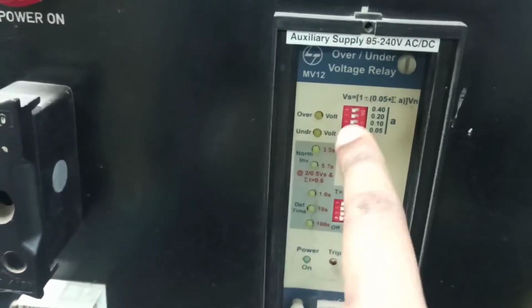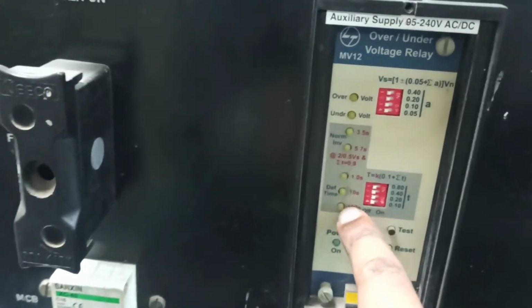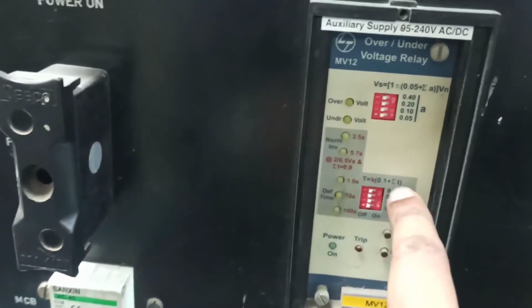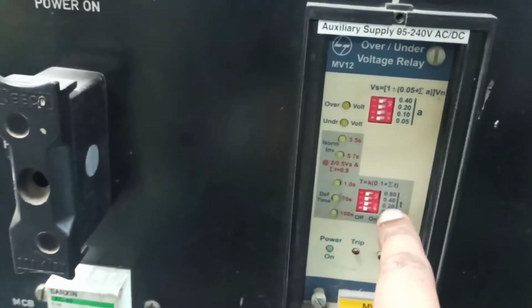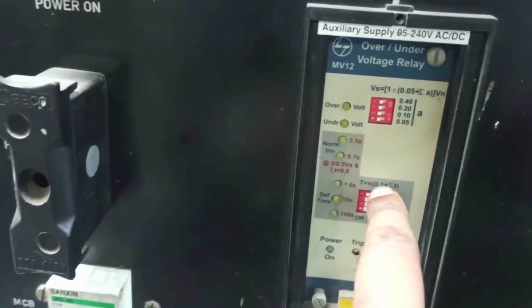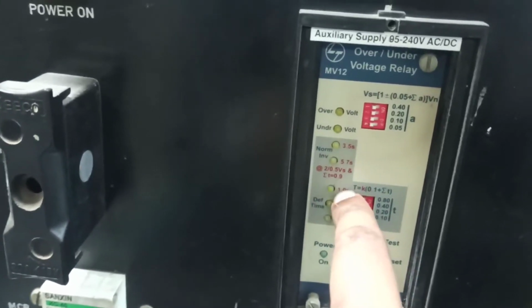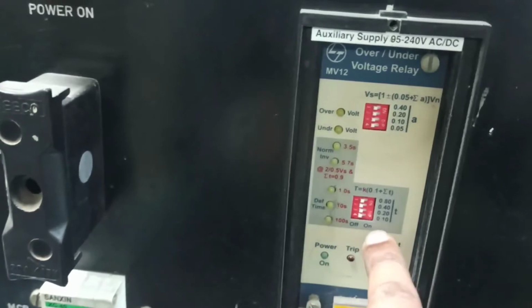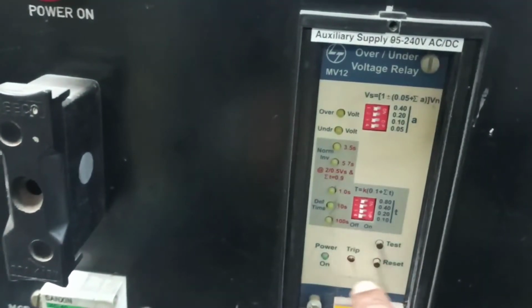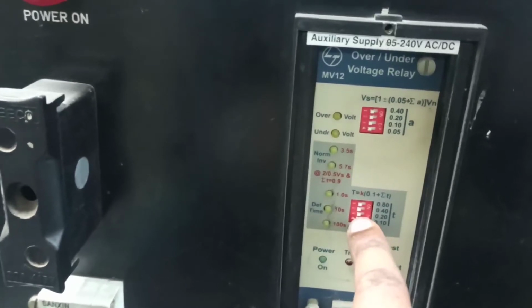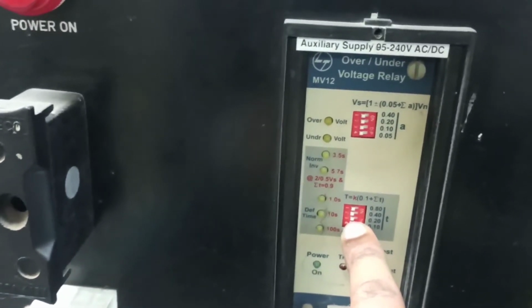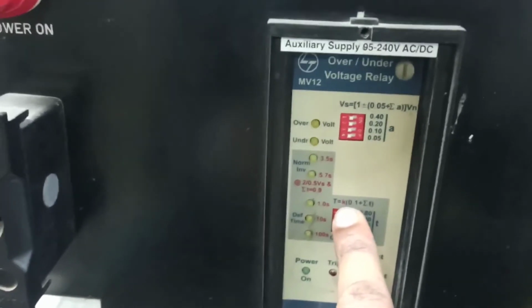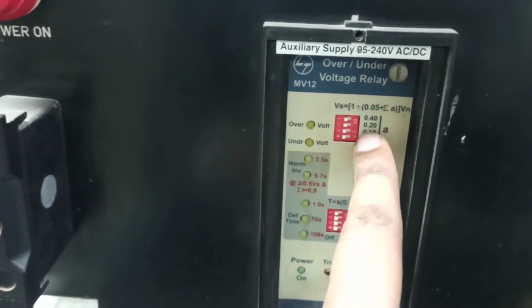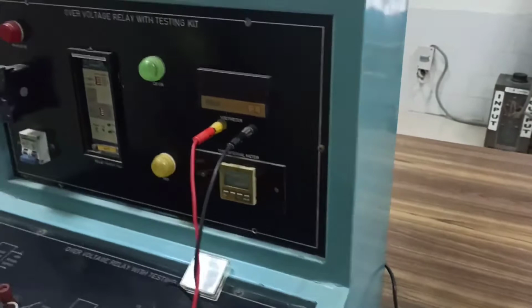K can be changed from inside of this kit. These are the K settings, 1, 10 or 100 seconds. And these are the times. So whatever time setting you are going to check, you can get the time setting from here. Okay, so you can set the voltage setting and the time setting, and then you can check your kit and plot the characteristics of the relay. So this is the working of the relay. If no switches are turned on, you can see from the manual what voltage corresponds to what setting.